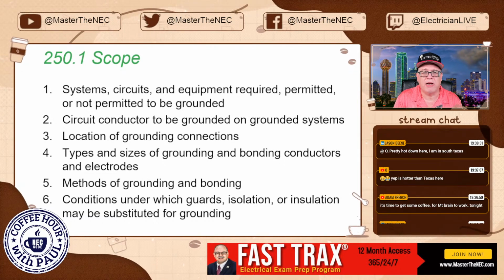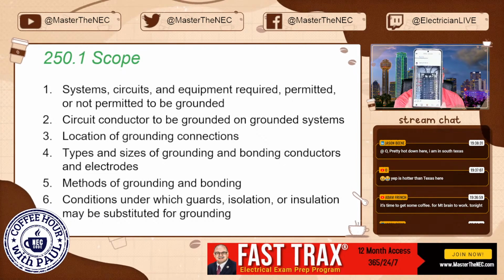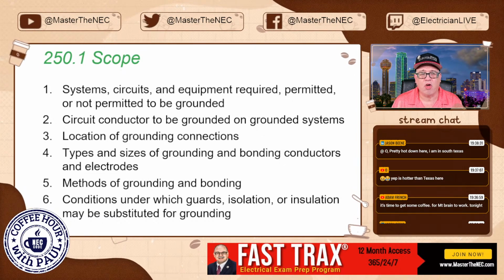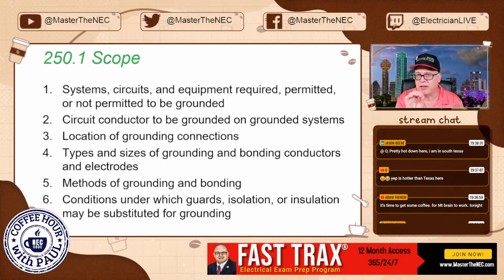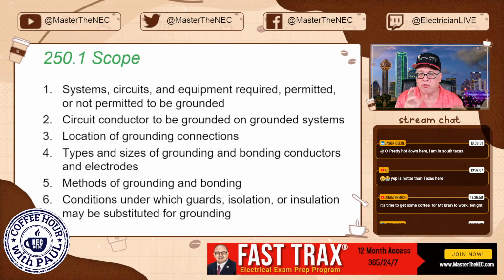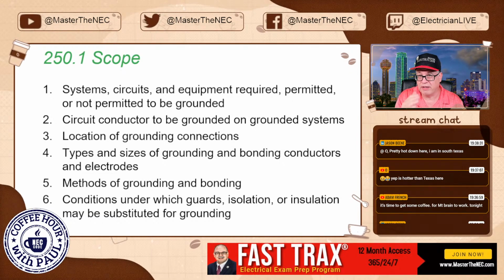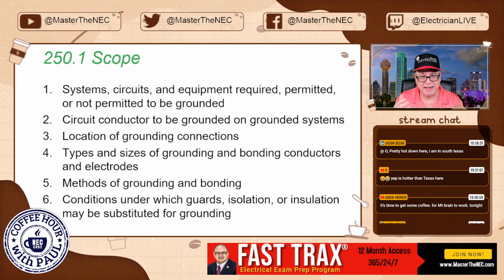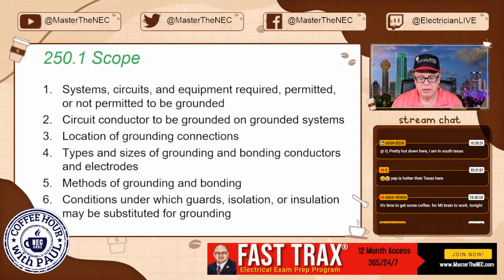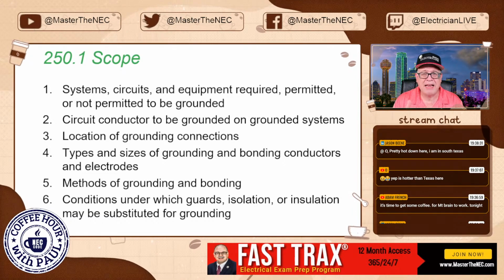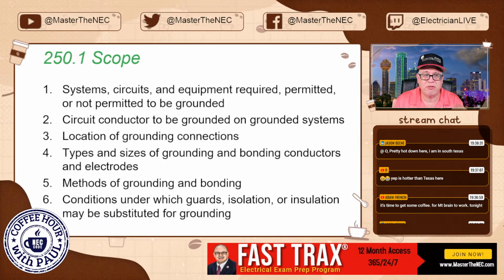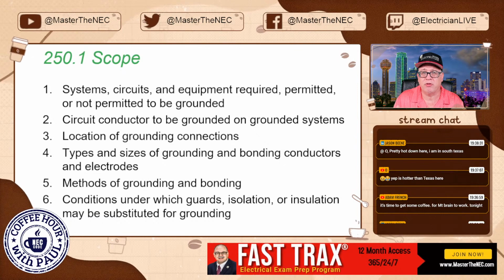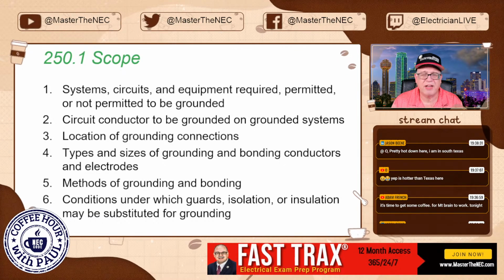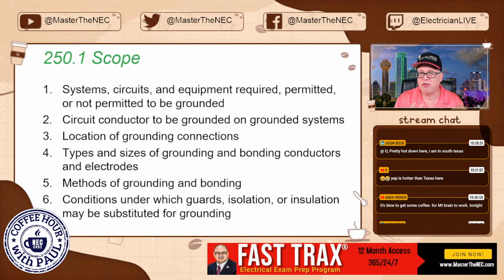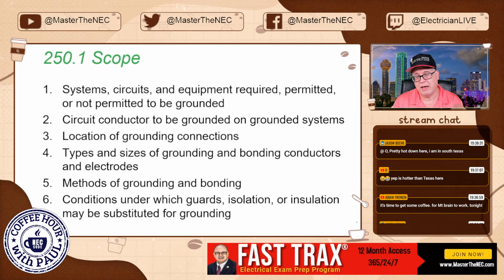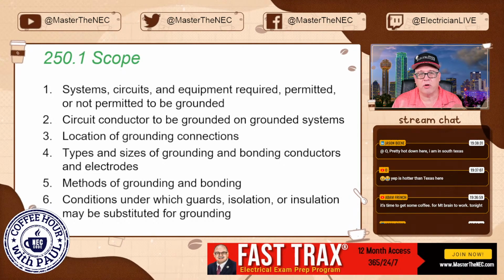I posted a picture, and you're not going to be able to see it, of a panel, a remote distribution panel. And I asked anybody if they saw what was wrong in that panel. Grounding and bonding is so fundamental: the green ground screw was in there connecting the neutral to the enclosure, but it's supposed to be isolated. The neutrals are isolated because it's downstream, right? Very few people mentioned it. I had people saying there wasn't the right size to the electrode. I don't know how you would even see that. Plus, this is a remote distribution panel. Why would you even say that? There were people saying all kinds of things that are not even germane to the question that was presented. At times people speculate and go down that rabbit hole.